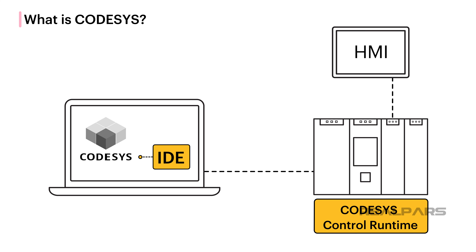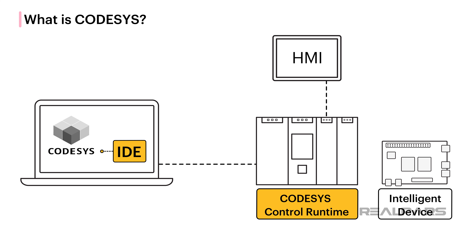The second piece of software is a runtime. The runtime executes applications developed in the Codesys Development System and serves the visualizations for those applications to clients. The Codesys runtime is typically installed on a PLC, but can be installed on any intelligent device that meets the runtime's minimum requirements, such as a Raspberry Pi. When the runtime is installed on a device, we say that the device is Codesys-compatible, since the device can execute Codesys applications.